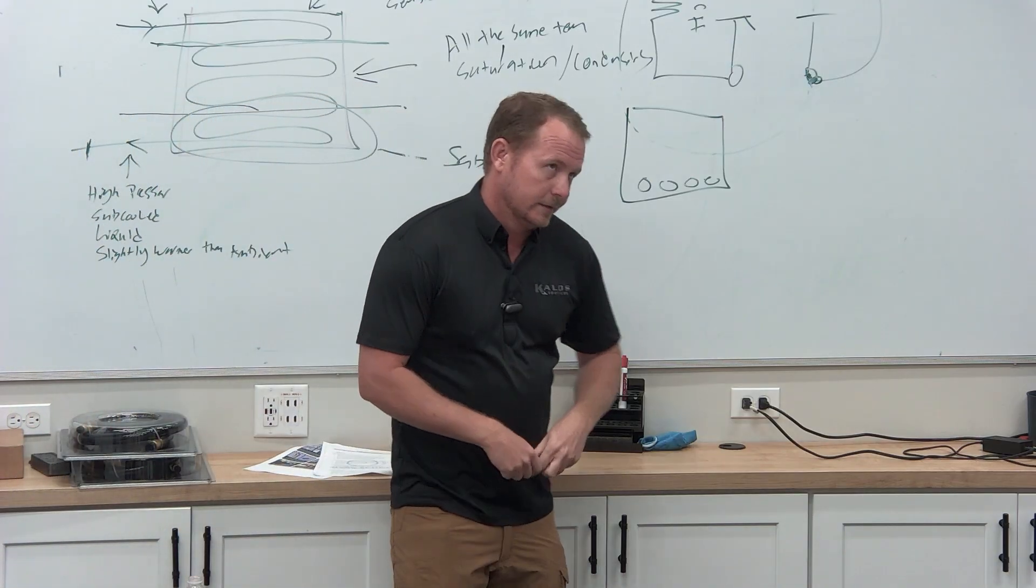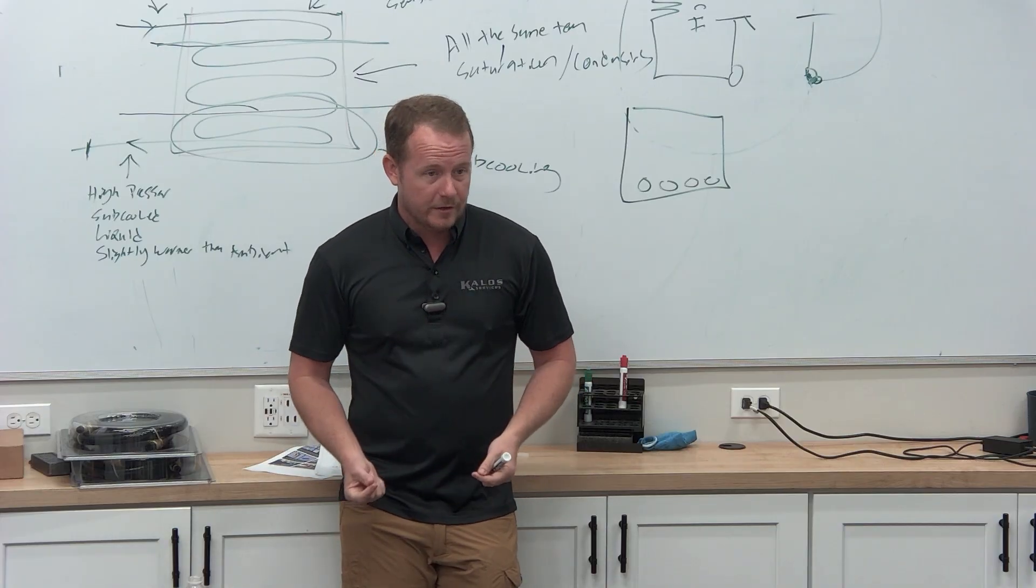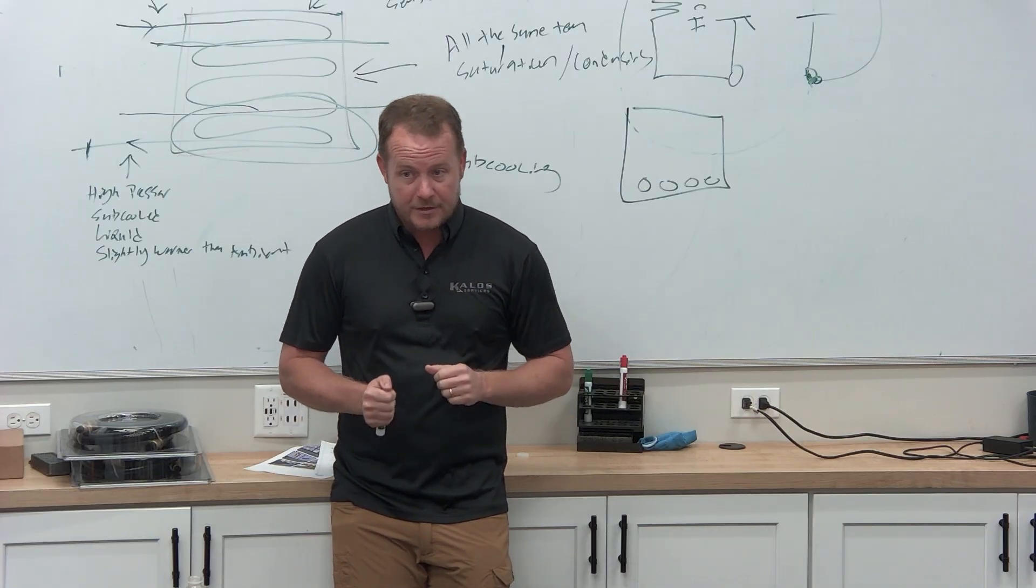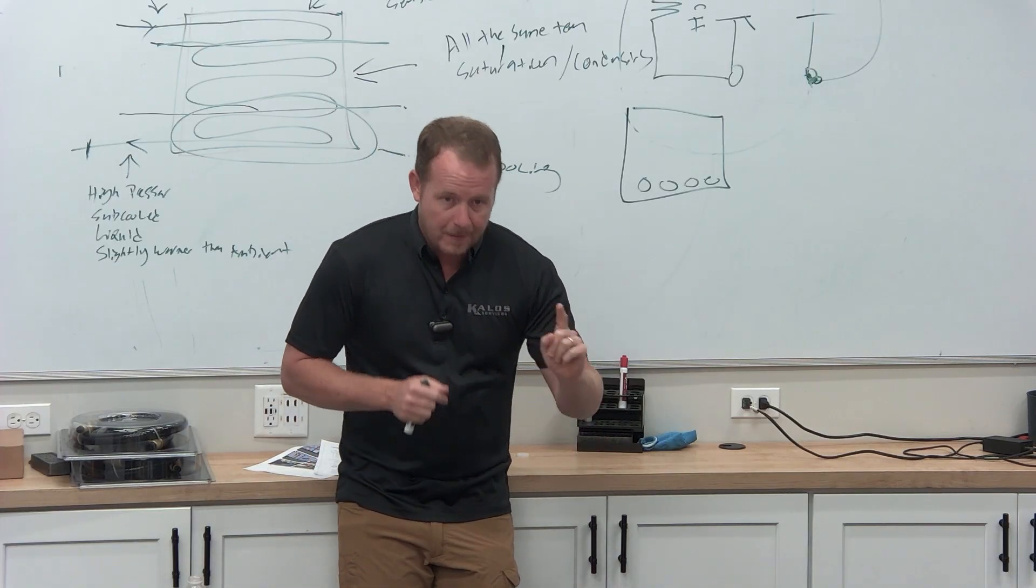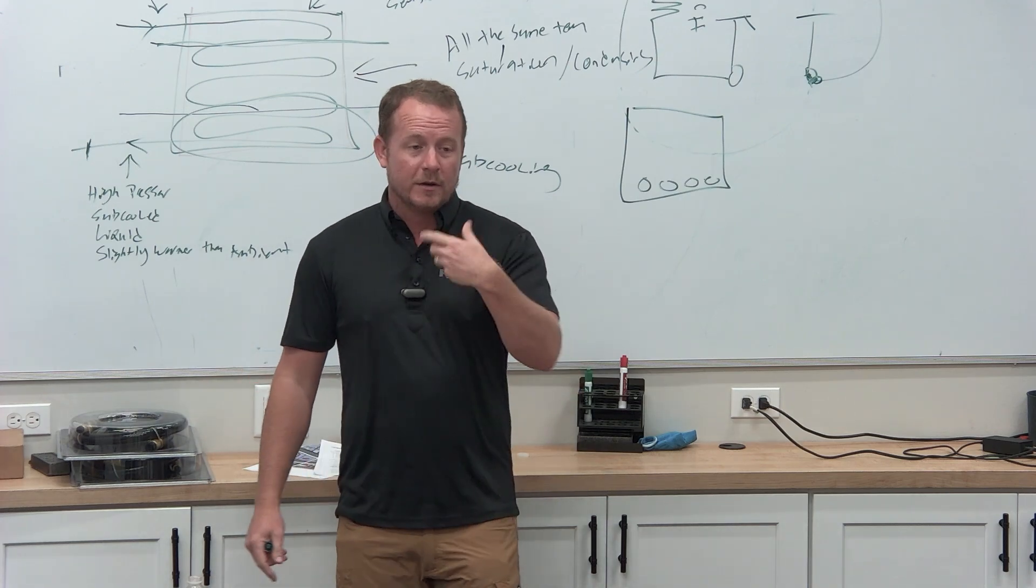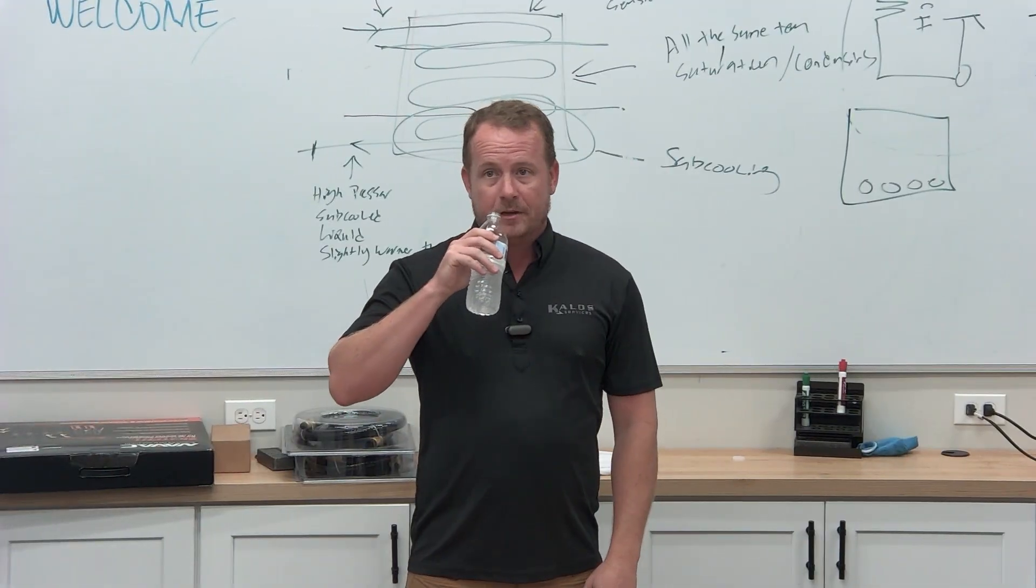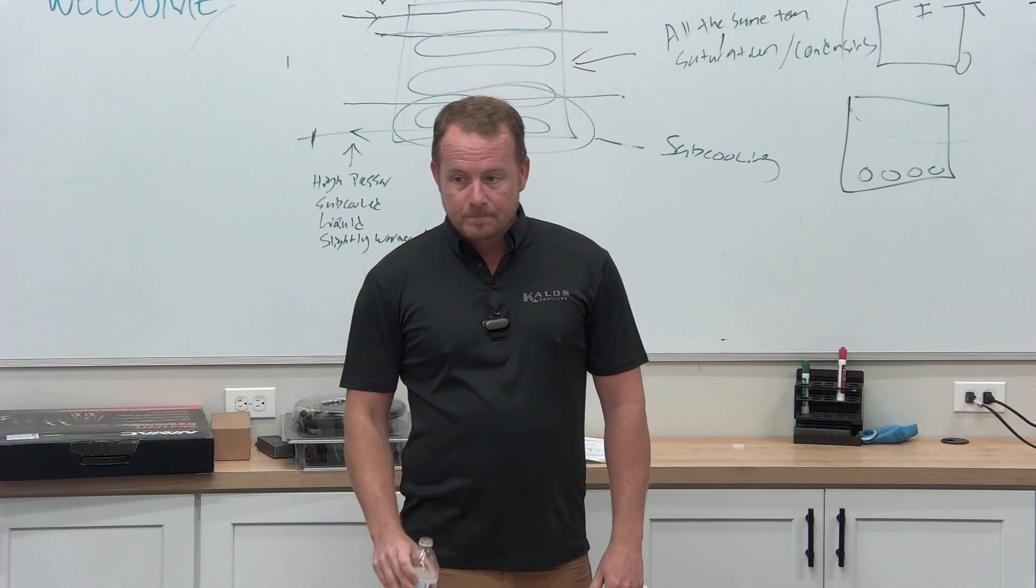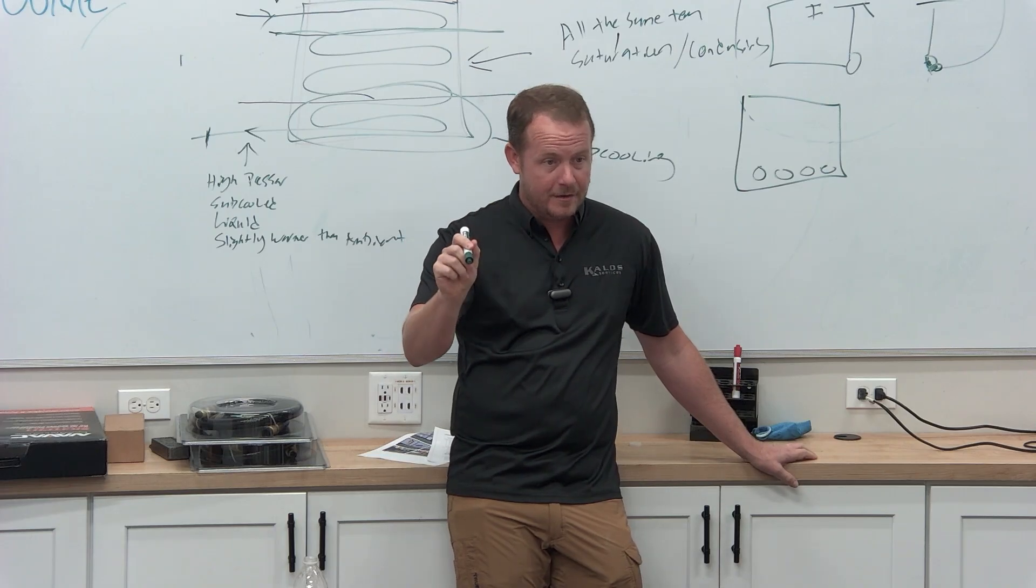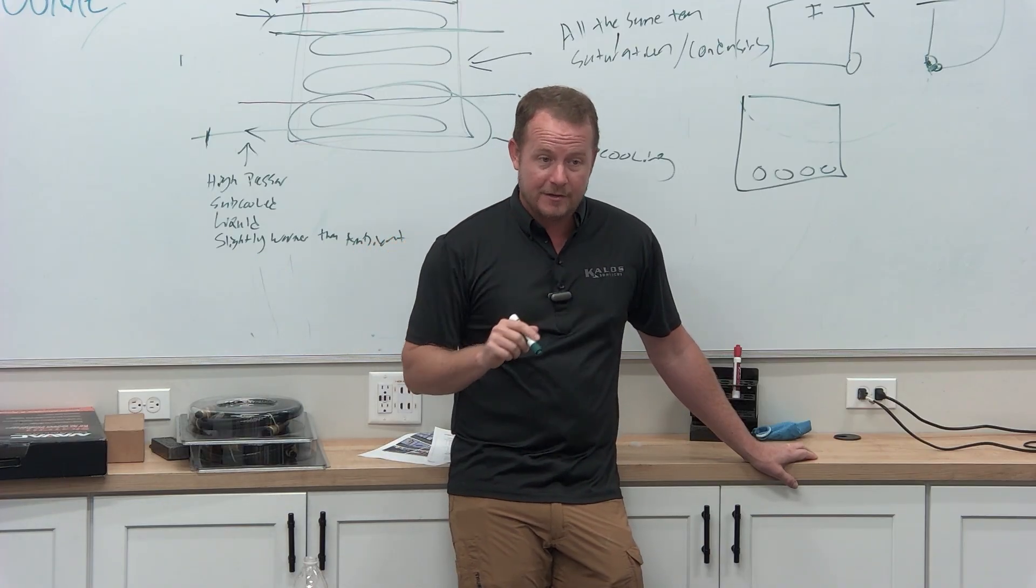Cool. Other than that, obviously, you know patience and setting charge. When you're doing things, like replacing parts, you always reconfirm the original diagnosis. You always do a good solid visual inspection, and you're going to do the full measure quick profile. Because you want to try to see what caused the problem. Another thing to mention, always use your scale to weigh in refrigerant. Always use your scale to weigh out refrigerant. Always. Not only so you don't overfill the tank. That's one reason, but that's not even the biggest reason. Say you went to install a compressor, and you start weighing out the refrigerant, and you only take three pounds out of a four-ton system. Hmm. Well, what do you do? Leak search. Yeah, you stop. And do not proceed with that compressor until you've found the leak. And even if you don't find the leak, you don't just move on. Right? Because the reason that compressor died is probably because it was short on charge, and it overheated to death.